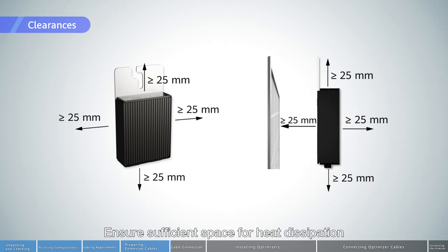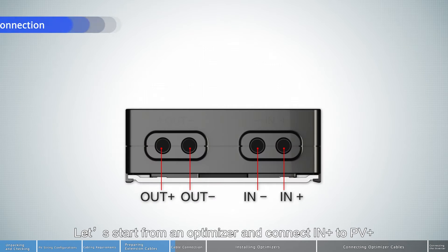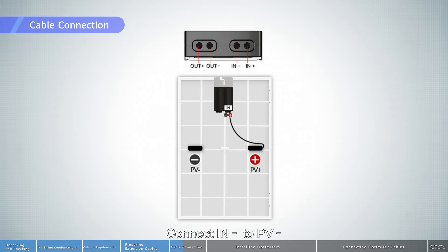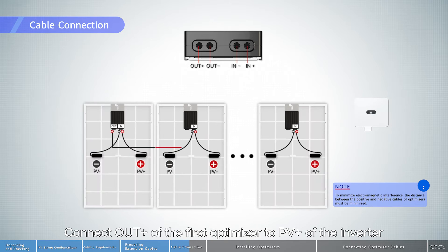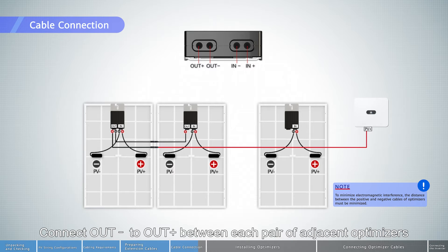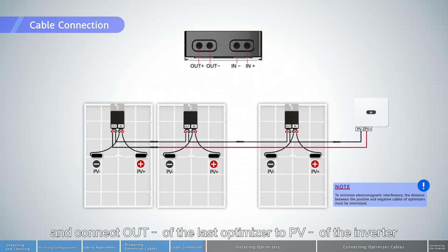Ensure sufficient space for heat dissipation. Starting from an optimizer, connect the input positive to PV positive, and connect the input negative to PV negative. Connect the output positive of the first optimizer to PV positive of the inverter using the extension cable. Connect output negative to output positive between each pair of adjacent optimizers.